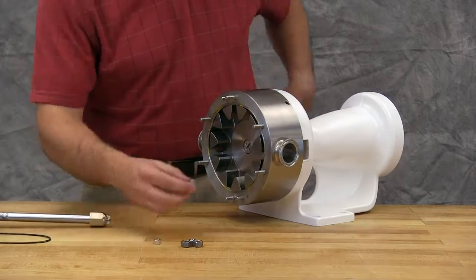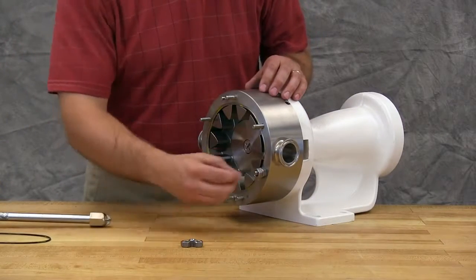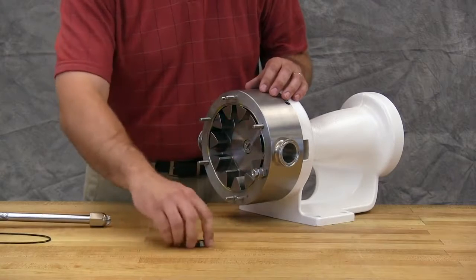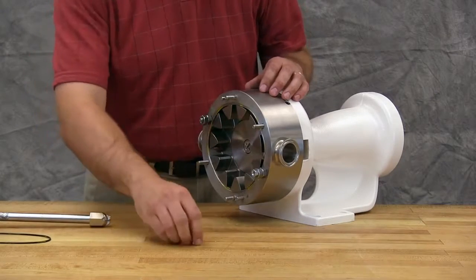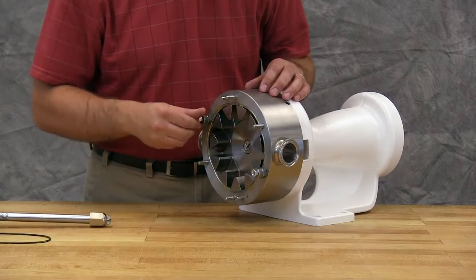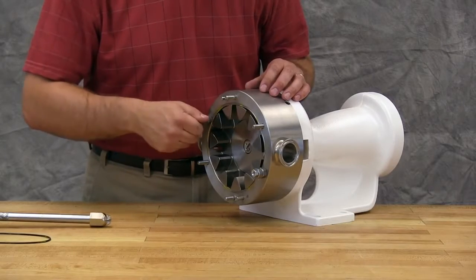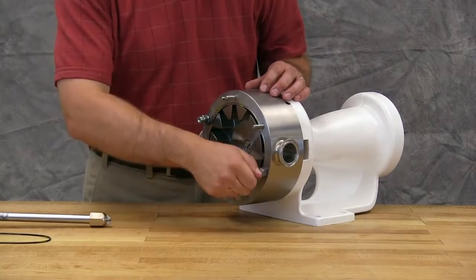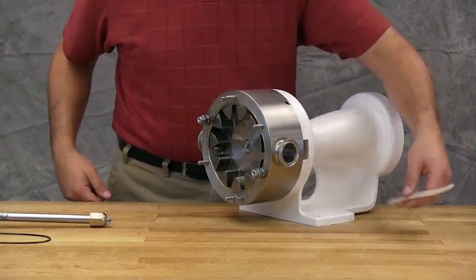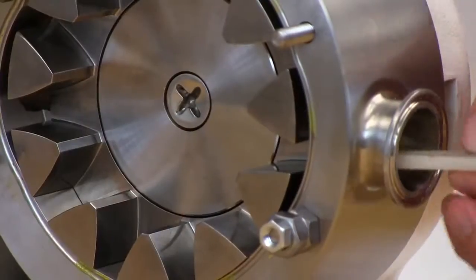Use two nuts to hold the casing in place during disassembly. These nuts should be located on opposite sides of the casing. A spacer or a couple of larger nuts will need to be used to compensate for the length of the casing studs. It is important the casing is secured during disassembly to avoid damage to the pump internals.